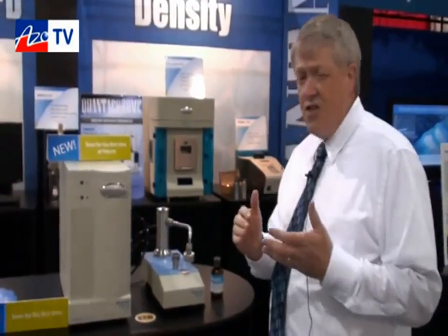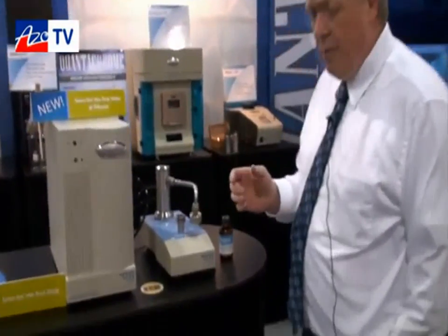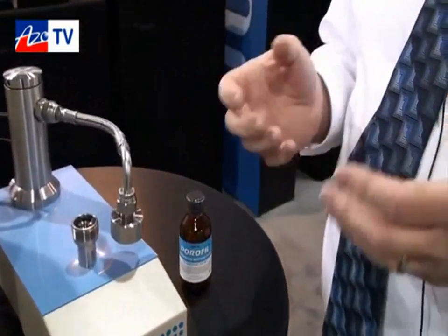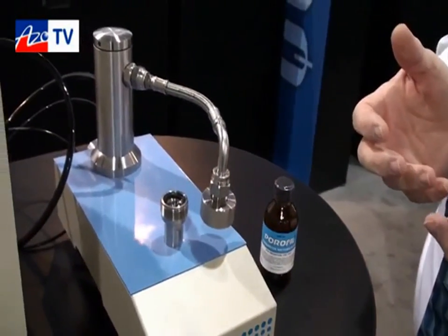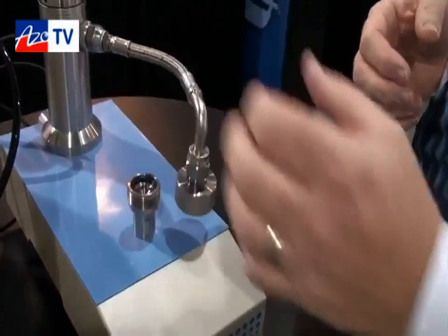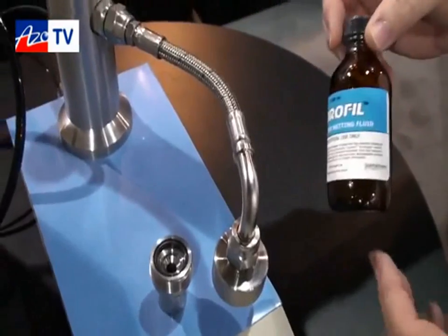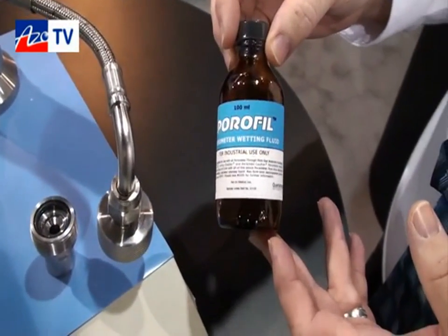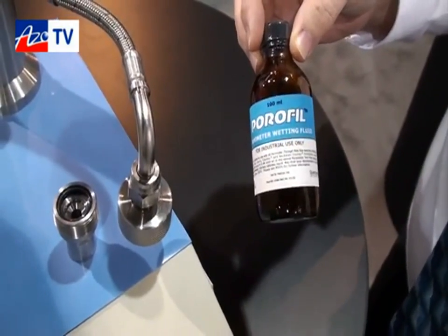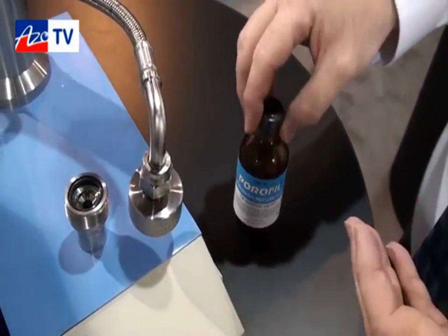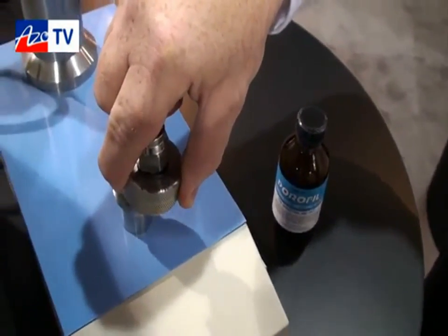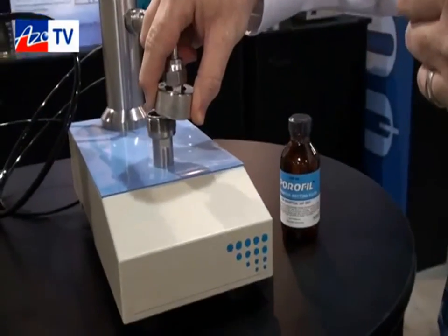And the technique is very simple. This sample is cut as a disc. If it's a standard filter, we have standard sample holders that take, for example, 47mm diameter filters. The sample is cut, if it's not already pre-cut, placed in the sample holder. Then it's wet with a special fluorocarbon liquid, which will wet even PTFE, but it won't swell cellulosic material.